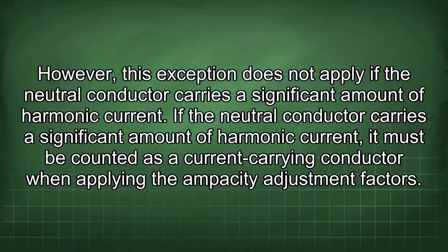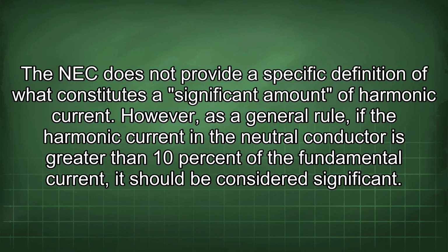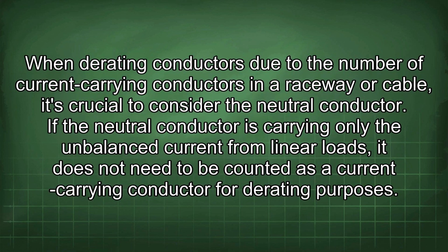However, this exception does not apply if the neutral conductor carries a significant amount of harmonic current. If the neutral conductor carries a significant amount of harmonic current, it must be counted as a current-carrying conductor when applying the ampacity adjustment factors. The NEC does not provide a specific definition of what constitutes a significant amount of harmonic current. However, as a general rule, if the harmonic current in the neutral conductor is greater than 10% of the fundamental current, it should be considered significant. When derating conductors due to the number of current-carrying conductors in a raceway or cable, it's crucial to consider the neutral conductor.